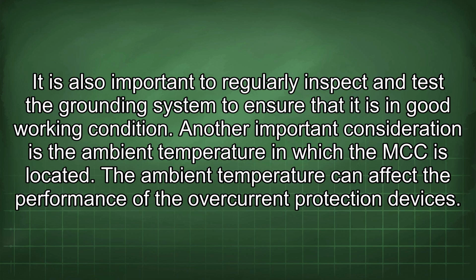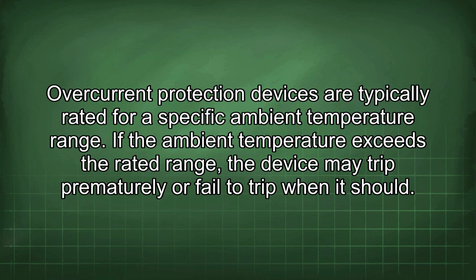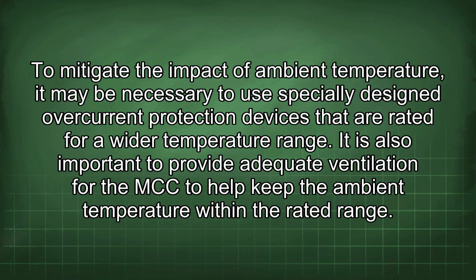Another important consideration is the ambient temperature in which the MCC is located. The ambient temperature can affect the performance of the overcurrent protection devices. Overcurrent protection devices are typically rated for a specific ambient temperature range. If the ambient temperature exceeds the rated range, the device may trip prematurely or fail to trip when it should. To mitigate the impact of ambient temperature, it may be necessary to use specially designed overcurrent protection devices that are rated for a wider temperature range. It is also important to provide adequate ventilation for the MCC to help keep the ambient temperature within the rated range.